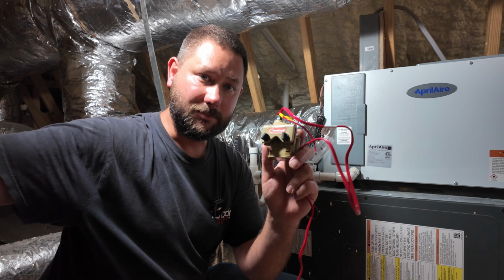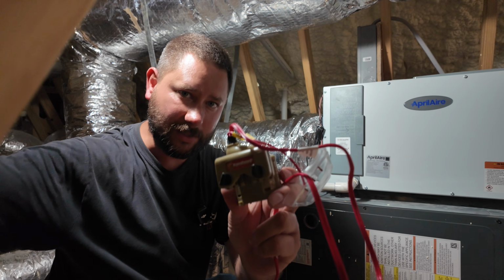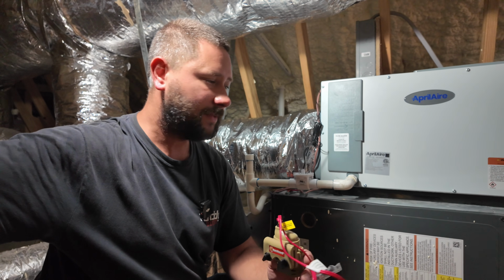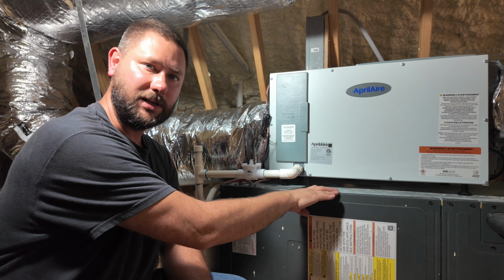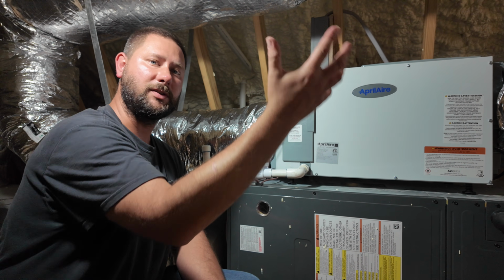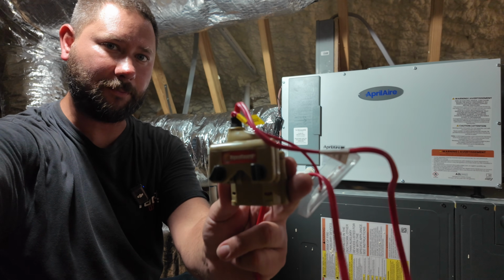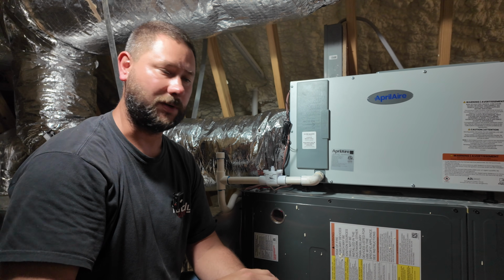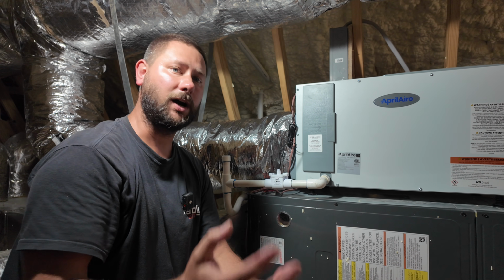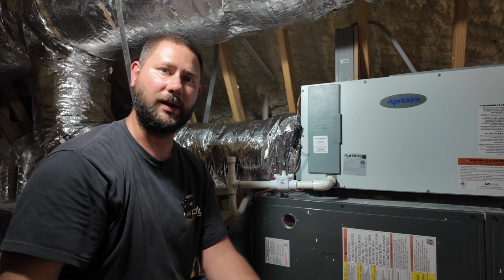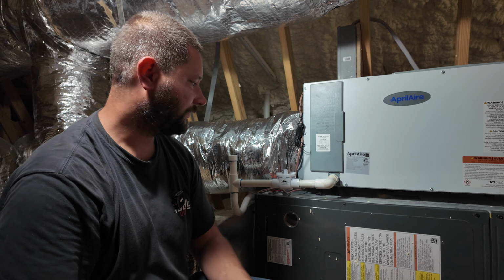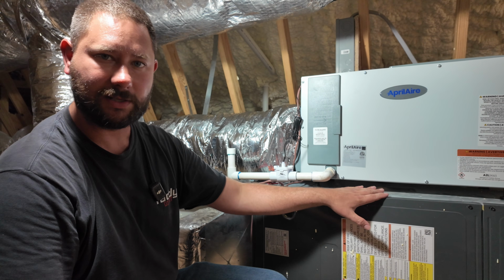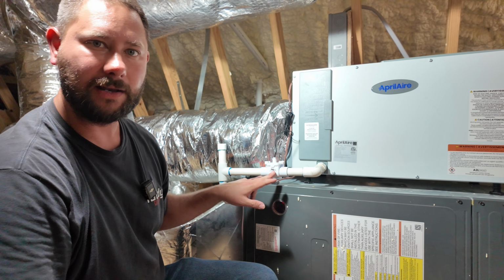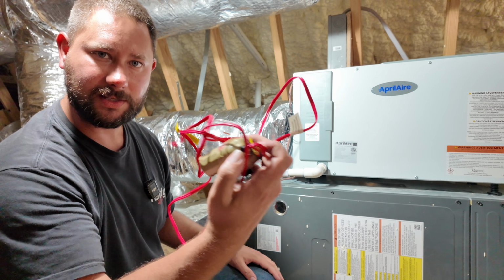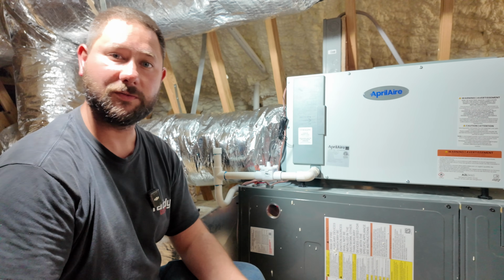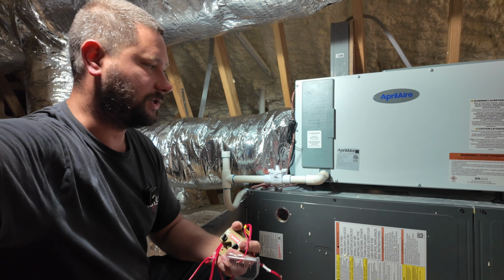And there we go. Make sure you install a float switch. You can install one of these, which sits in a pan — you can install a pan underneath the dehumidifier, or build a pan, put the dehumidifier in it, and install this in that pan, then wire it in to where it says float switch. That way you have a way to cut off the dehumidifier so you don't have water pouring out of your pan into your ceiling. We didn't build a pan, so we used an inline float switch instead — it'll do the same thing: cut off the dehumidifier and prevent water from damaging the ceiling.